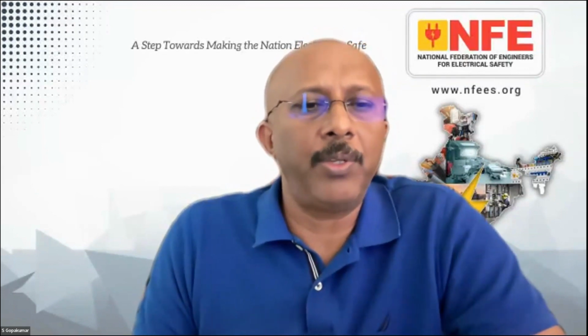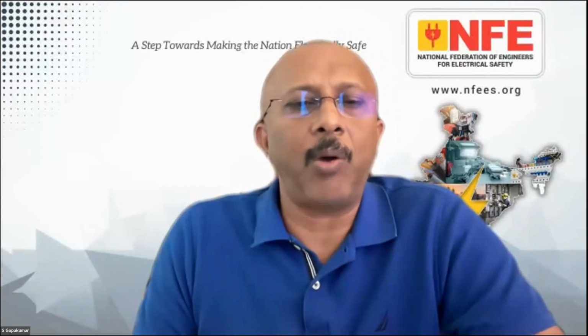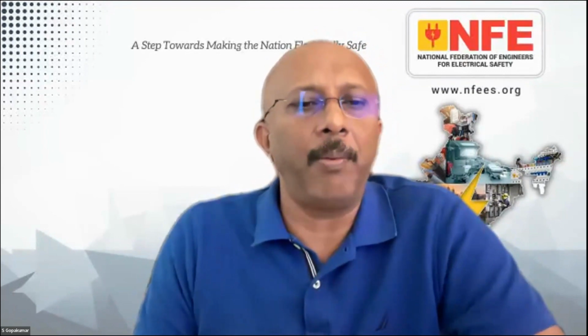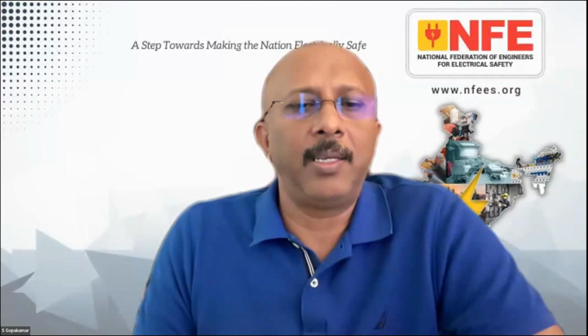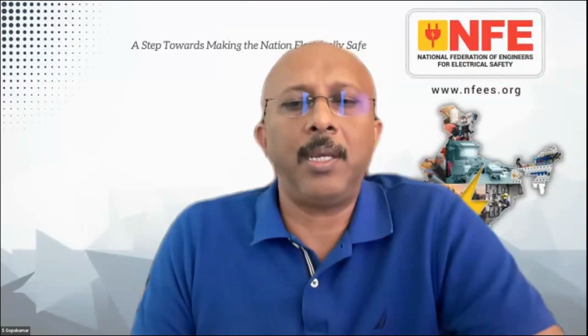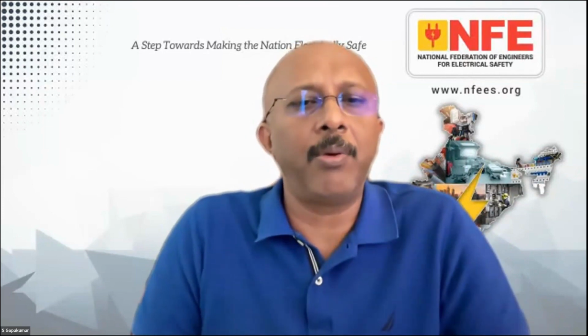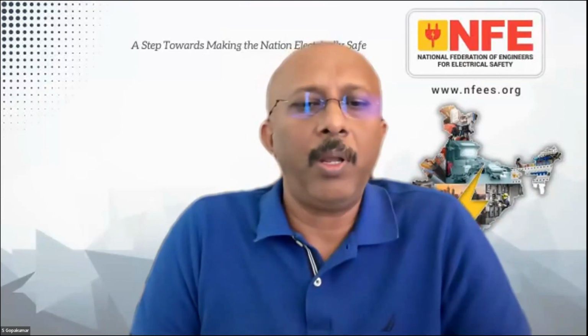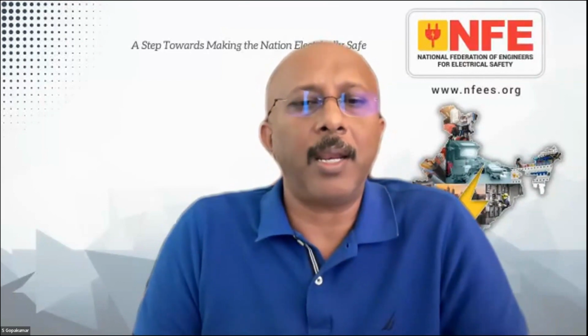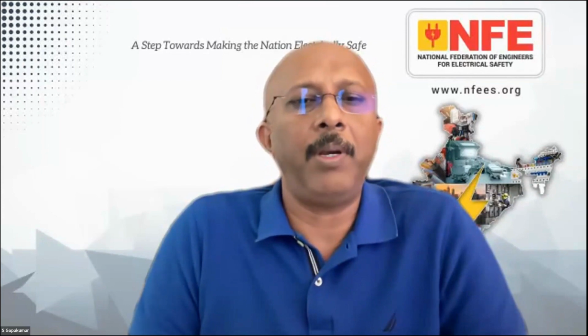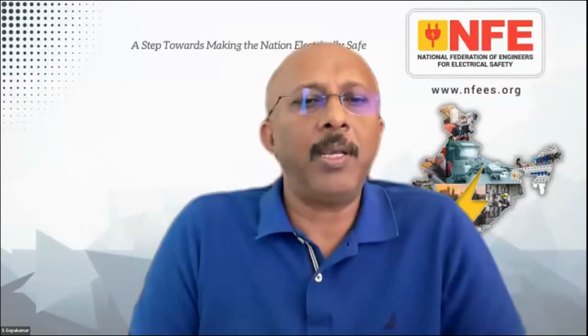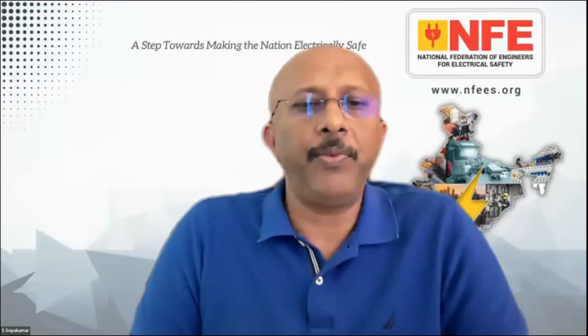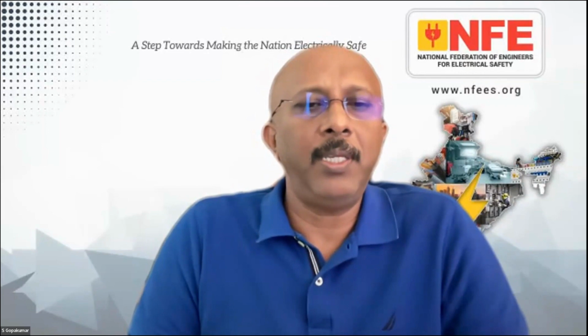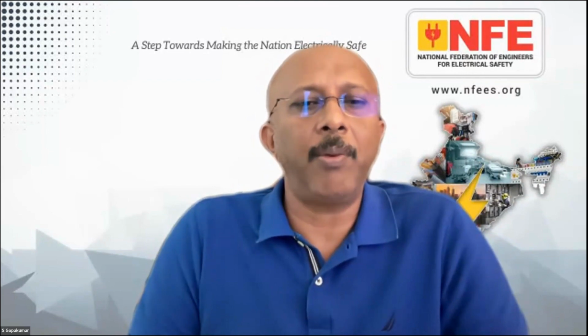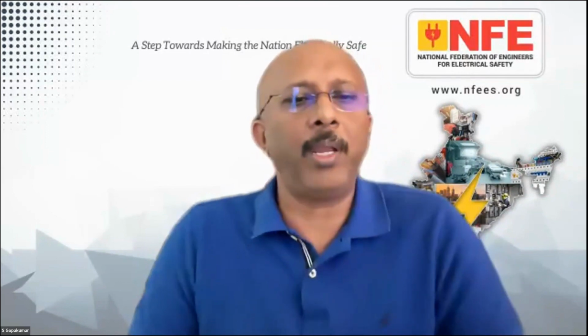Shiva Prasad, I think your question was related to, in case of any mistakes, how to identify the gap, what is required and what is not available. Am I correct? Yes. Actually, this is a real challenging problem in India, because this test or this information itself is new in the market, even though it was written in all the standards. There is no habit of making a circuit proper until now, because we don't have the habit of measuring these impedances. In my experience, out of 100 measurements which we make, in almost 50-60 cases the sizing of the protective devices and conductors does not match the requirement of the standard.